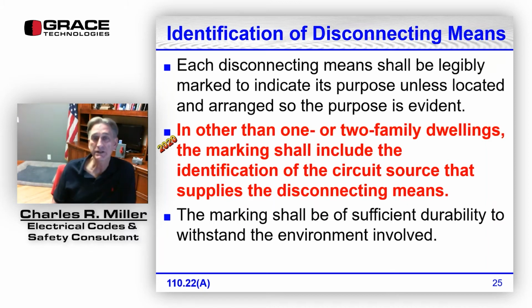And when I'm teaching NFPA 70E, arc flash and electrical safety in the workplace, I'll ask the students, all right, the label says this breaker, this circuit goes to this equipment. And I'll ask in class, can you turn that off and trust your life that it is correctly labeled? And the correct answer, and the answer I always get, is no, you can't trust your life to that. It's a great place to start, but you cannot trust your life to the information on the label being correct. In other than 1 and 2 family dwellings, it has to include the identification of the circuit source that supplies the disconnecting means. The marking has to be of sufficient durability to withstand the environment.